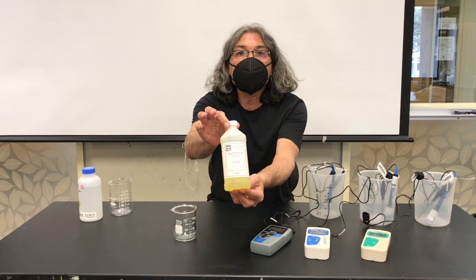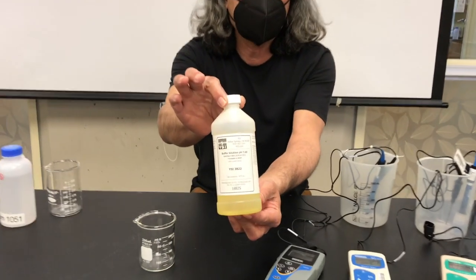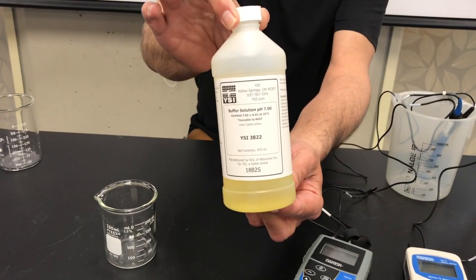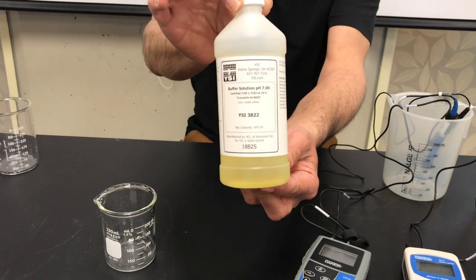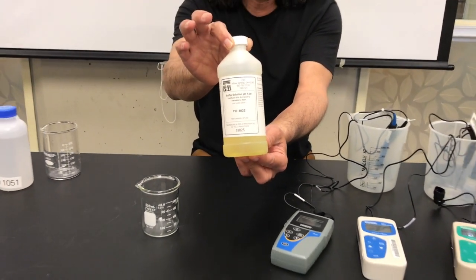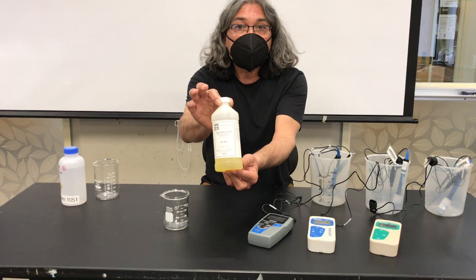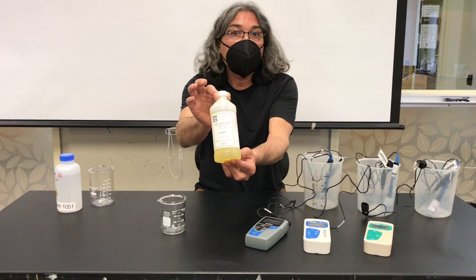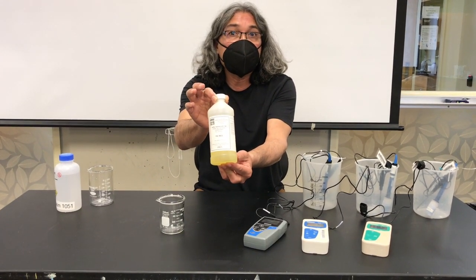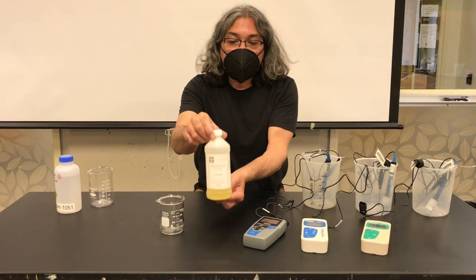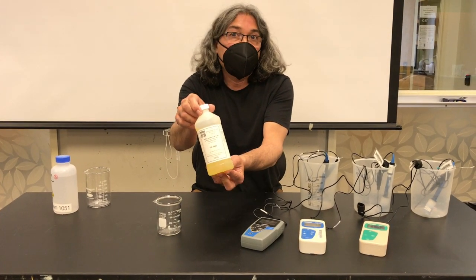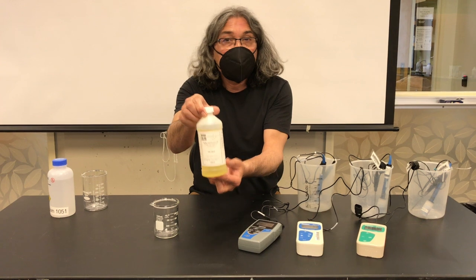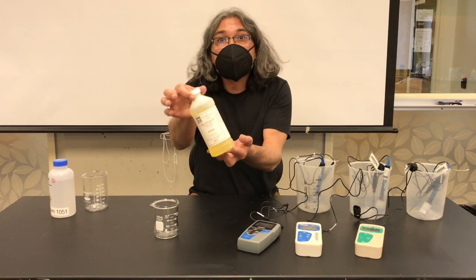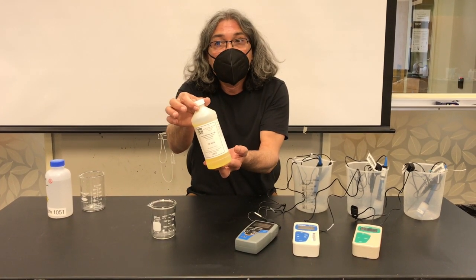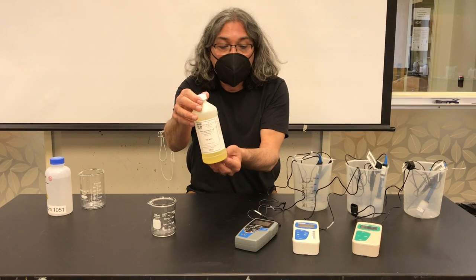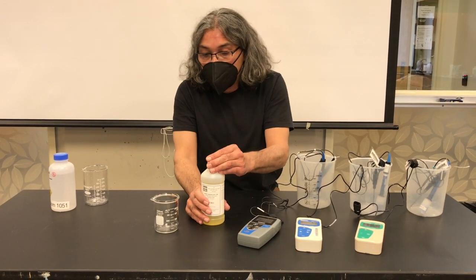This is one of the buffers that we use to calibrate the pH meters. We used three buffers when we did the calibration. We used a pH 4 buffer, a pH 7, and a pH 10 buffer. So all of these have been calibrated with 3 points. The only reason I'm using this is that it's convenient for me right now because I have it, right? But assume that this is the sample that you need to measure when you're doing your pH measurements.